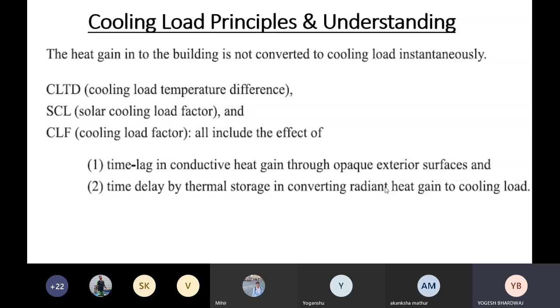Here I can define them in quite some detail. So CLTD is a theoretical temperature difference that accounts for the combined effect of inside and outside air temperature difference, daily temperature range, solar radiation, and heat storage in the construction assembly, the building mass. So it is the theoretical temperature difference that takes into account all these things, including building thermal mass. It is affected by orientation, tilt, month, day, hour, latitude. These CLTD factors are used for adjustment to conductive heat gains from wall, roof, floor, and glass.